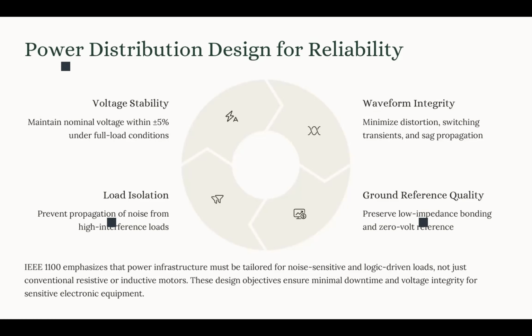Okay, so there is a margin defined in this standard for variation in the amplitude of the voltage, the RMS of the voltage actually. So we have to maintain our nominal voltage within plus or minus 5% in a full load condition. That's important. Full load condition.